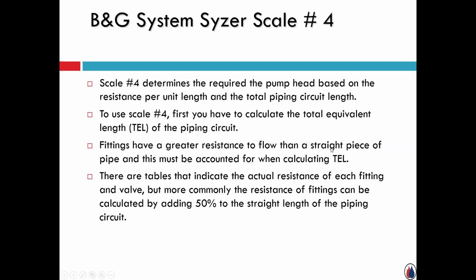To use scale 4, first you have to calculate the total equivalent length, or the TEL, of that circuit. And all they're referencing is that fittings can offer, and we kind of touched on it last week a little bit, but fittings will offer a little more resistance than straight pipe. They'll actually have an equivalent how many feet of TEL relative to if I was a straight piece of pipe.